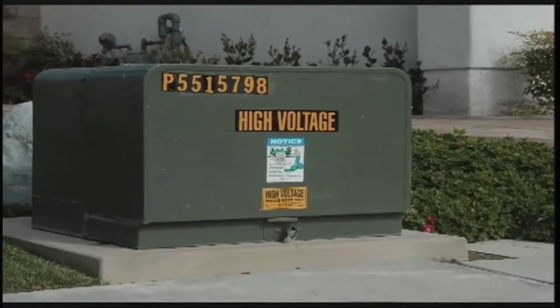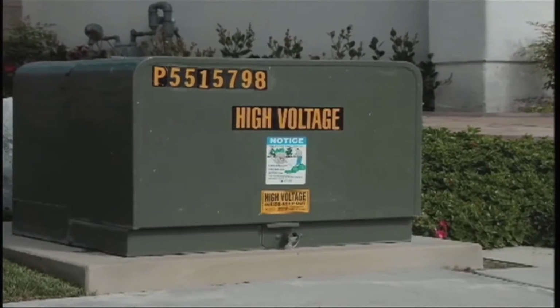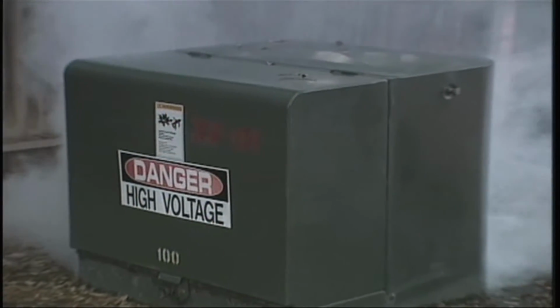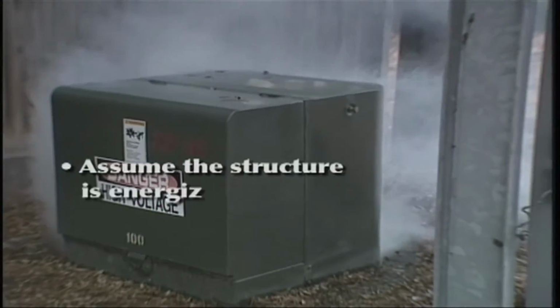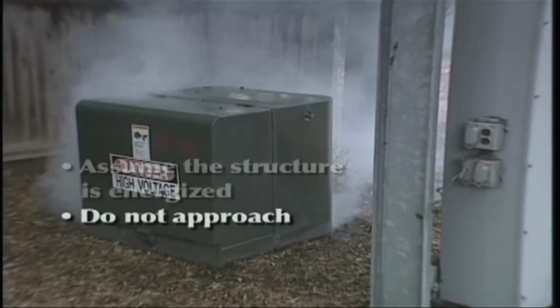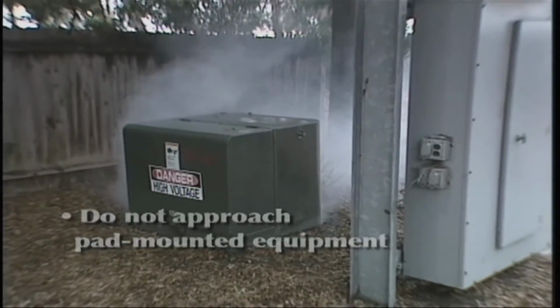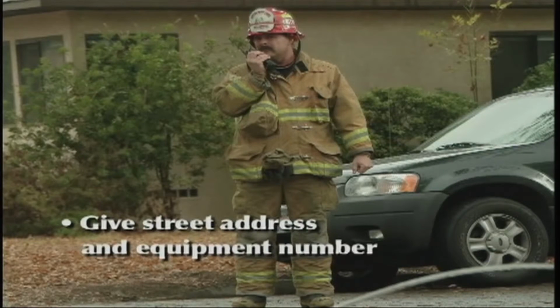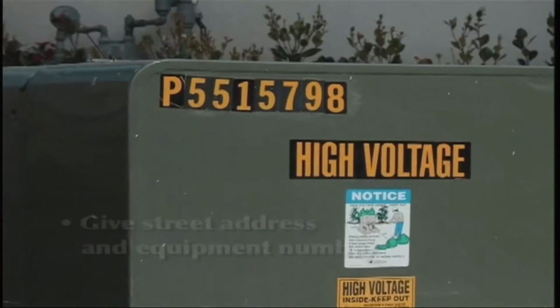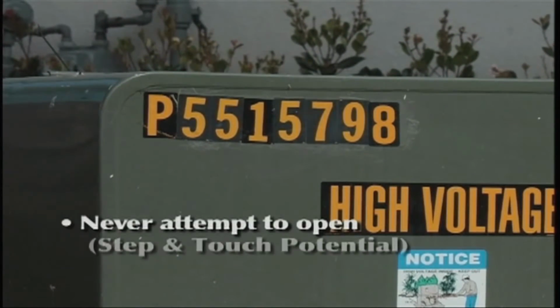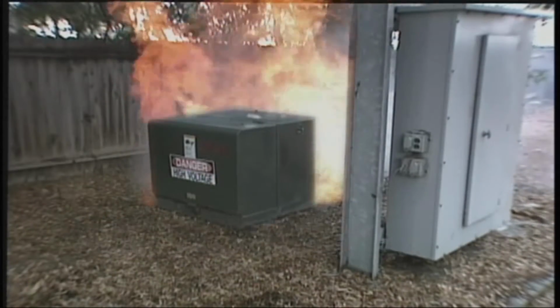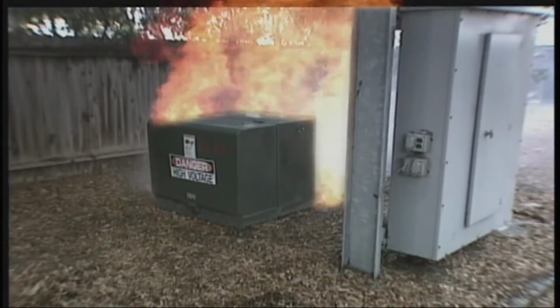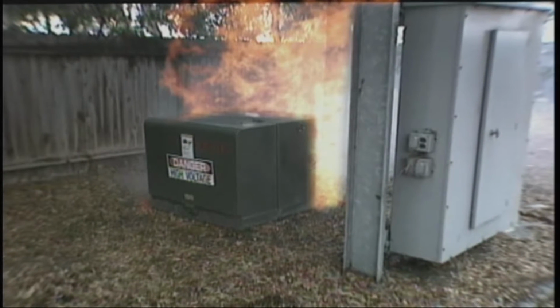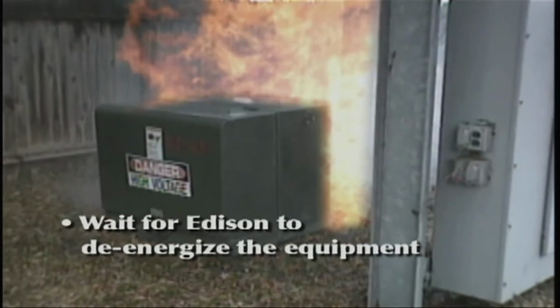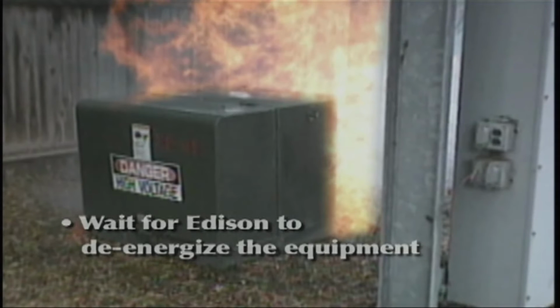commercial neighborhoods. When responding to an incident involving a pad-mounted structure, here's what to do. Assume that the structure and anything touching it is energized, and do not approach the pad-mounted equipment. Call Edison and give the operator the street address and any equipment number you can see on the pad-mounted unit involved. Never attempt to open the doors. Remember step and touch potential. If fire is involved, treat the situation as you would any Class C fire. Protect exposures and wait for Edison to de-energize the equipment before fighting the fire or attempting a rescue.